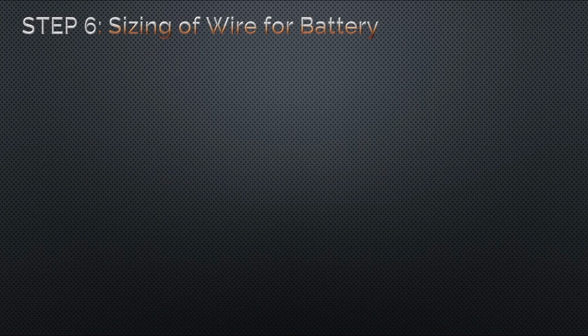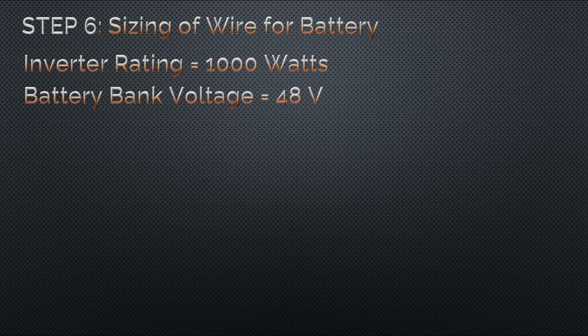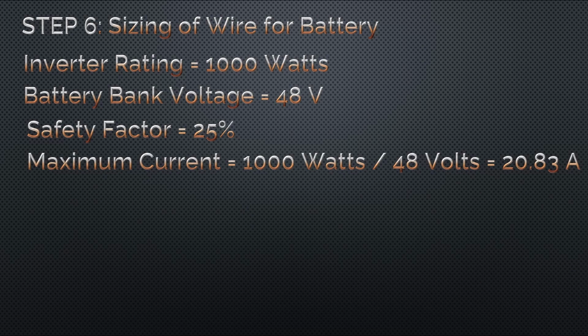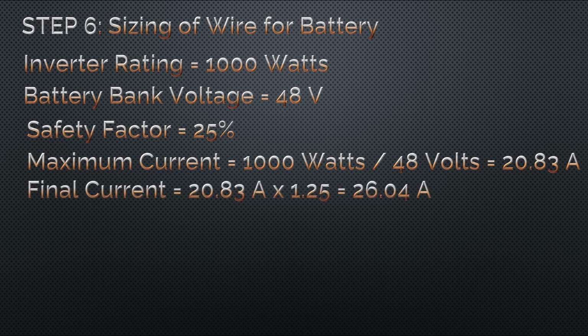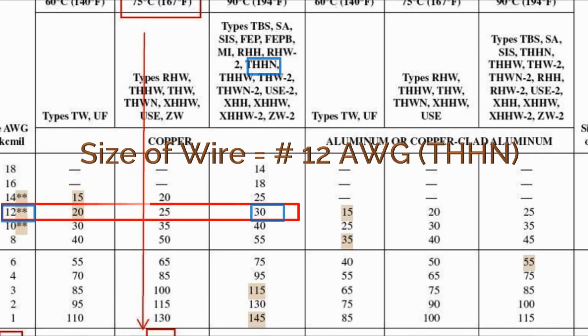To size the feeder wire for the battery bank, you have to consider the inverter rating, battery bank voltage, and the application of 25% safety factor. The 25% factor is also a safety measure to ensure that the wires can handle the loads under sustained or continuous operation without overheating. Now we will compute first the maximum current, and this will be equal to 20.83 amperes. Then apply 25% safety factor, and we will get 26.04 amperes. Now if we look in the ampacity table, we will use number 12 AWG THHN with 30 ampere full load current rating.